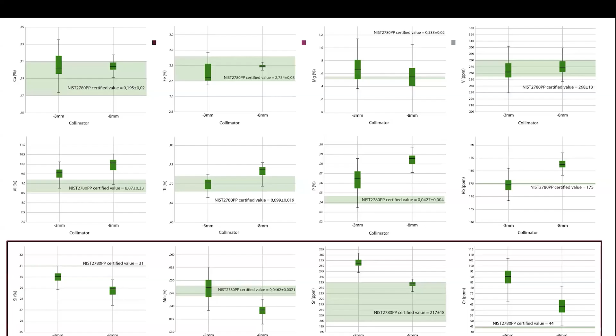Now, even though we could verify the precision of the device, because through the years we have almost the same result, the same values for the elements, so we have verified the precision and repeatability of the device, we still face the challenge of the accuracy of the results. For that reason, several comparisons with other laboratory techniques, mainly such as wavelength dispersive X-ray fluorescence, have been carried out to obtain the slope and intercept in order to evaluate the accuracy and systematic bias of the equipment, and also to obtain the R-squared values for the data precision for ceramic analysis.